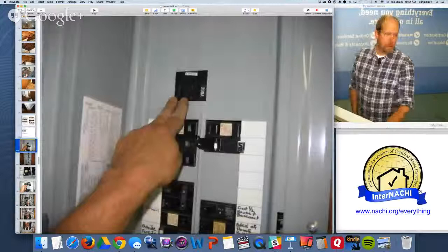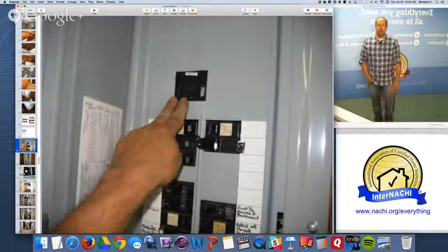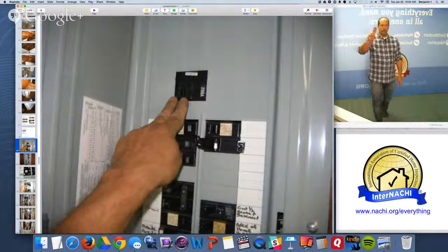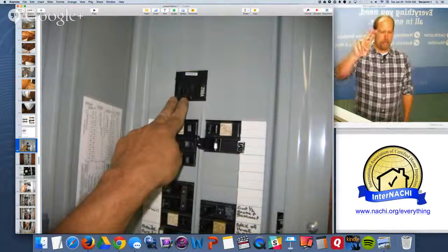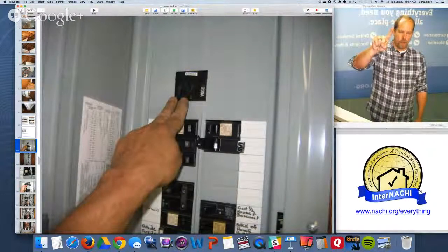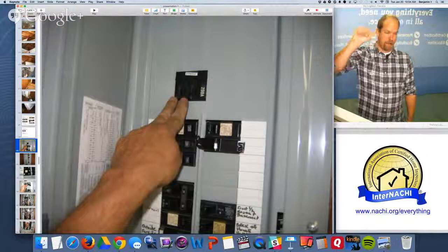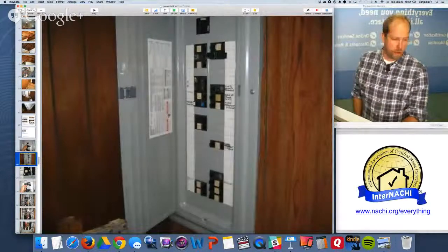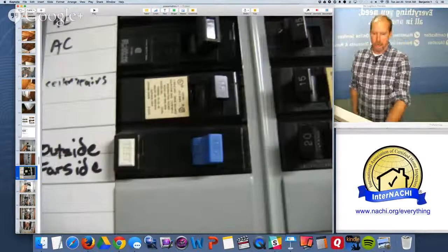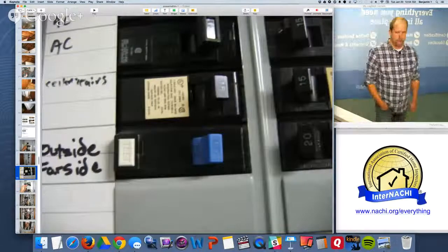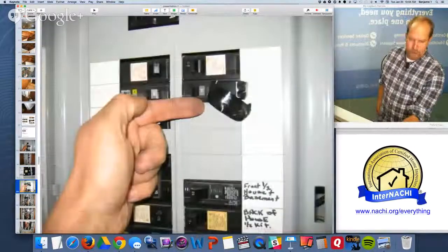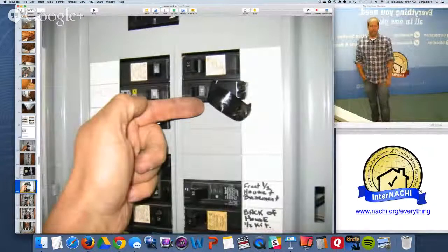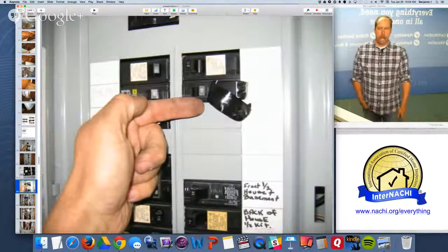Electrical: I identify the service coming in on the main disconnect, whether it's labeled, and take a picture of my hand on it — two fingers, 200 amps. Every breaker should be labeled — we don't have every breaker labeled here. There's a ground fault breaker that I tested and it works. There's one breaker I identified, prior to even touching the panel, as being turned off manually — it wasn't tripped, it was turned off.